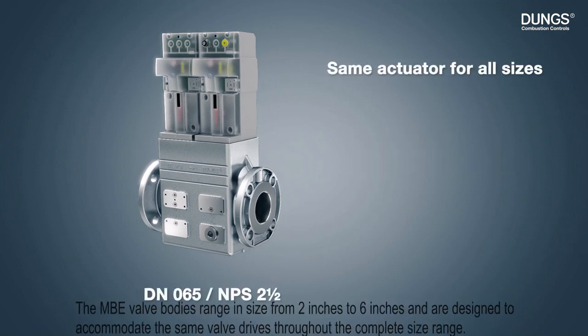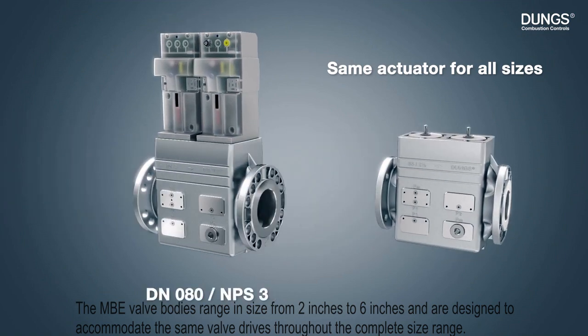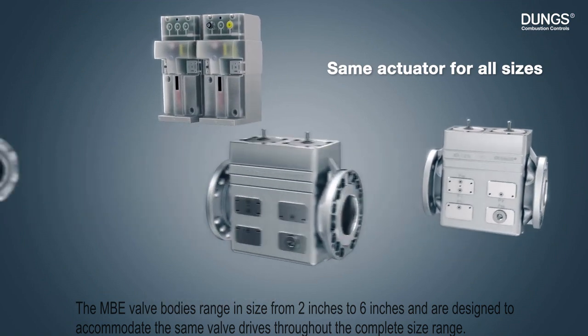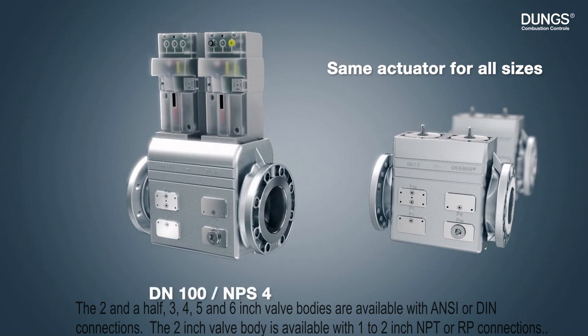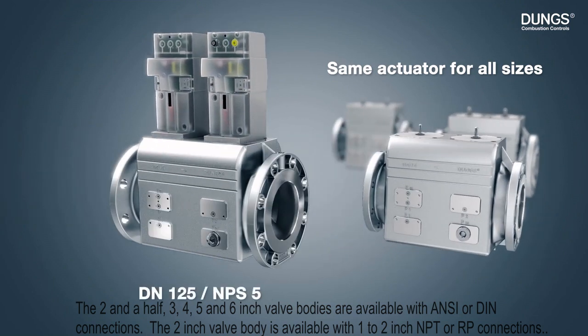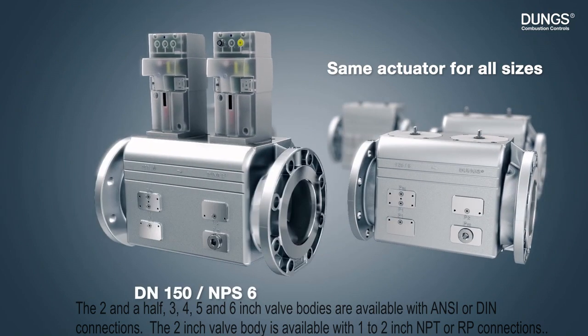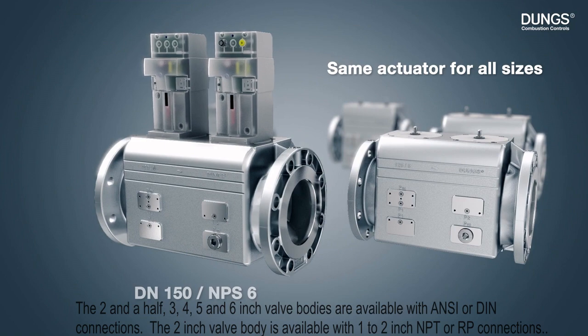The MBE valve bodies range in size from 2 inches to 6 inches and are designed to accommodate the same valve drives throughout the complete size range. The 2.5, 3, 4, 5, and 6 inch valve bodies are available with ANSI or DIN connections. The 2 inch valve body is available with 1 to 2 inch NPT or RP connections.